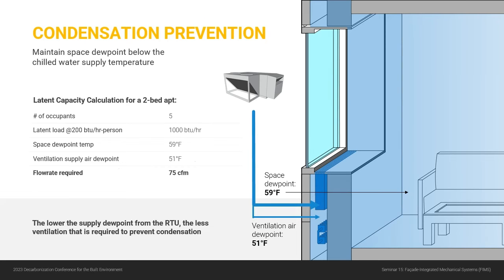Now, the idea here is we're preventing condensation, and so we have to design the system appropriately. And again, this looks very much like a chilled beam system. So the key is maintaining the space dew point below the chilled water supply temperature. And so we're relying on the ventilation air to do that. And so this is a quick calculation showing a 2-bedroom apartment with 5 people. If we're supplying the air at 51-degree dew point, we would actually need about 75 CFM to maintain that humidity in the space. So that's actually more than you require by code.